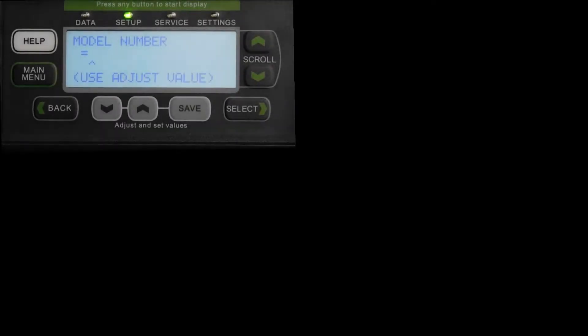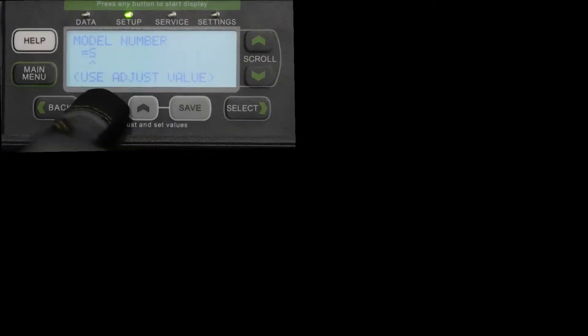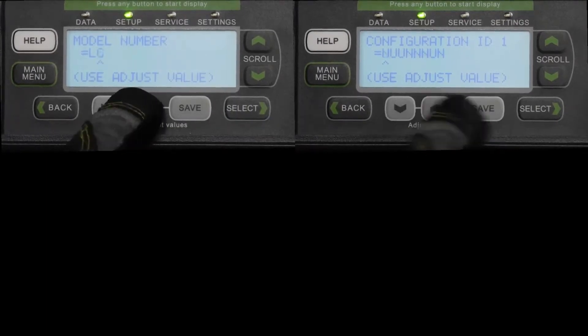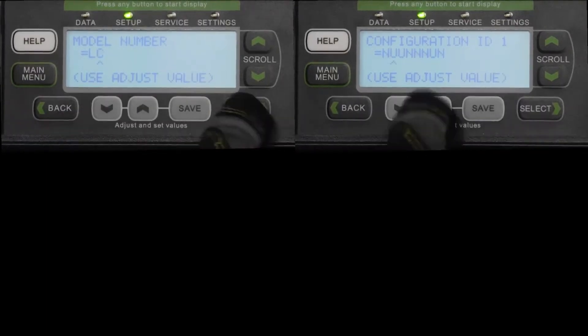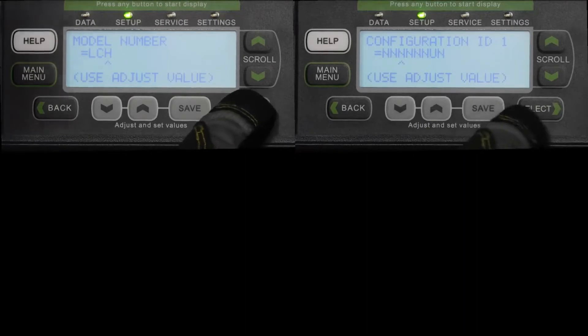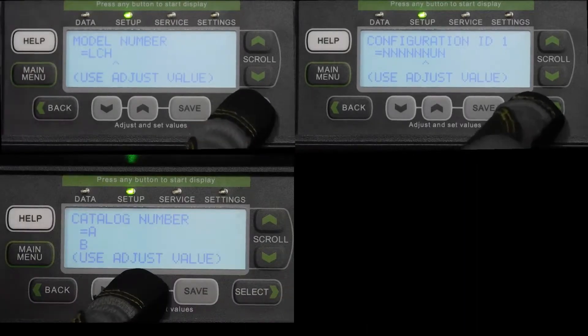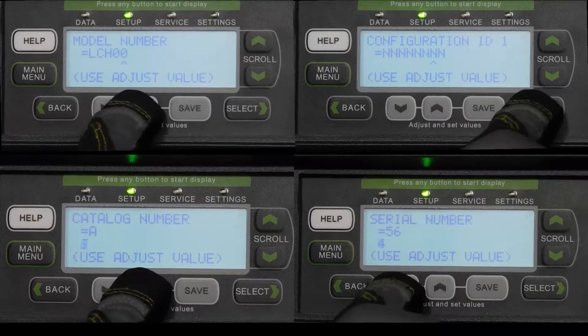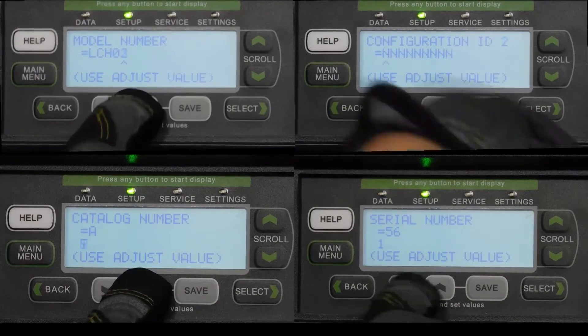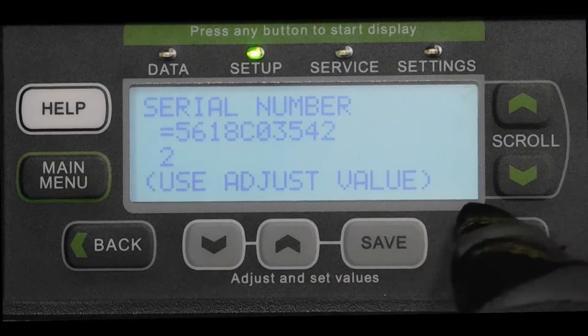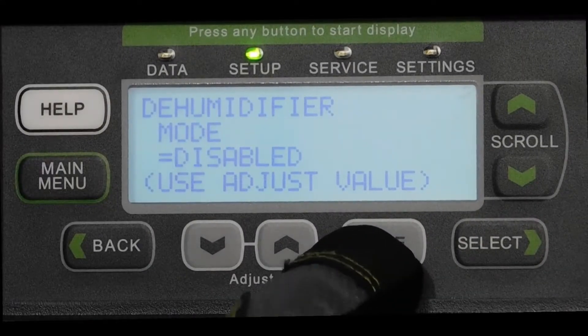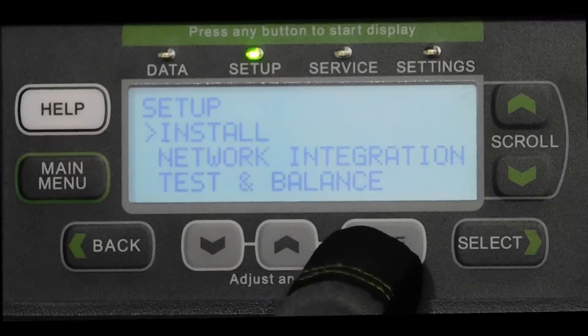After you press Save for the temperature reading, continue pressing Save through the rest of the menu path in order for the changes to take effect. As you do this, you will confirm — or if this is a replacement board, enter — the model number, configuration ID 1 and 2, catalog number, serial number, and finally the rooftop unit description in the control settings.